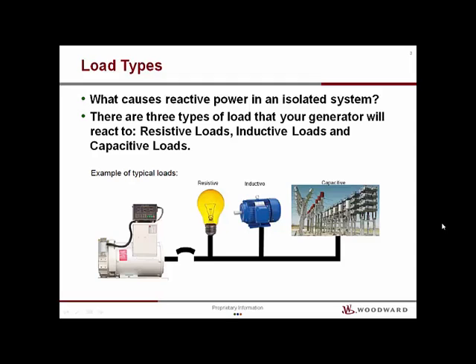What causes reactive power in an isolated system? Reactive power in an AC generator is caused by the load that is on the generator. The load types are resistive, inductive, and capacitive. Resistive loads consist of devices that are purely resistive in nature, with no inductive or capacitive reactance. These are physical devices consisting of the line resistance of the wires, baseboard heaters, and incandescent light bulbs. A purely resistive load will create a unity power factor, or a power factor of 1.0.